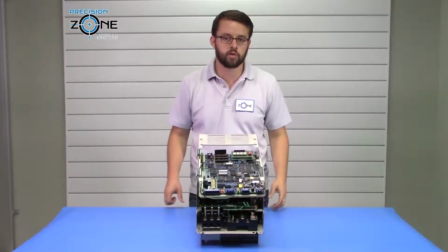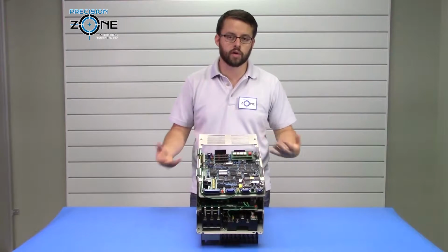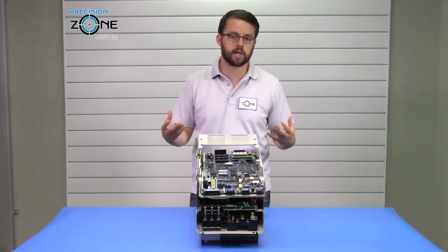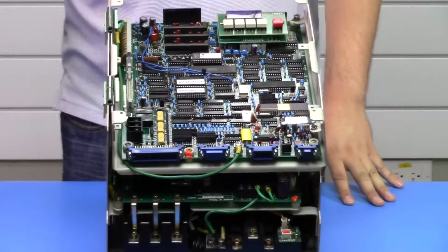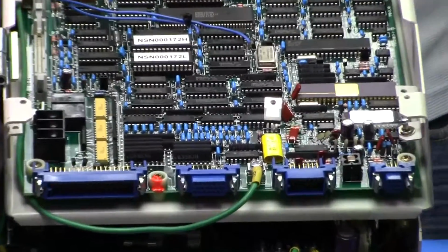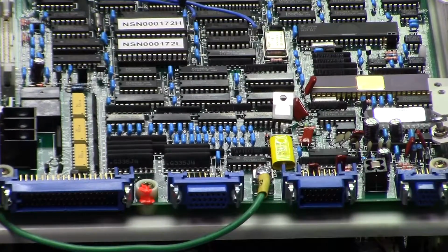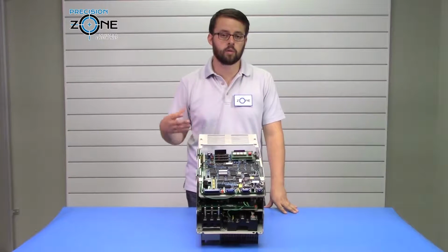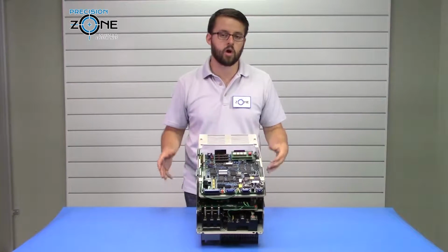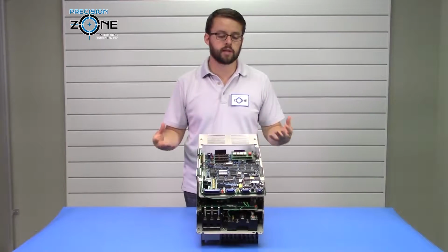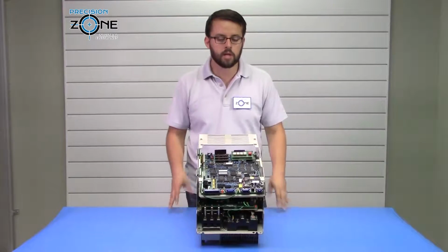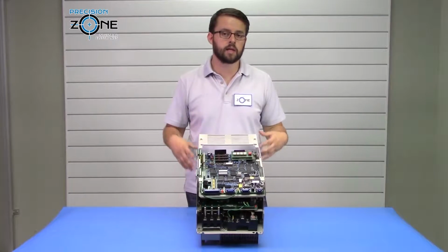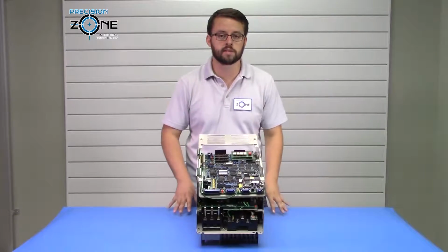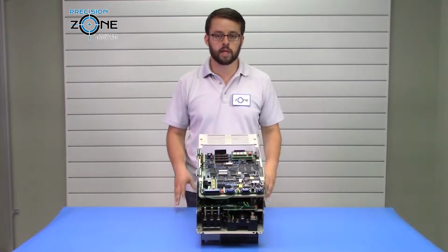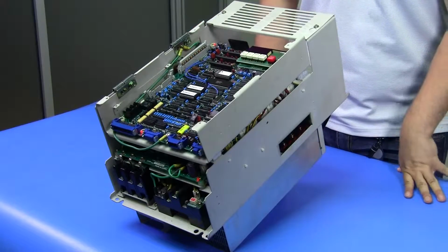So some of the alarms that you can receive on these are overcurrent alarms, which would be related to the motor or the cables going from the motor to the drive. If the insulation on those has deteriorated enough, then it would cause a short to ground and cause that failure. If you got the overcurrent issue during operation, then likely it could have caused the fuse to blow inside the drive, in which case you would get a fuse alarm as well.